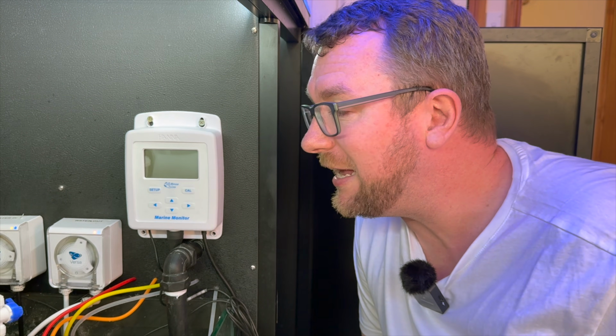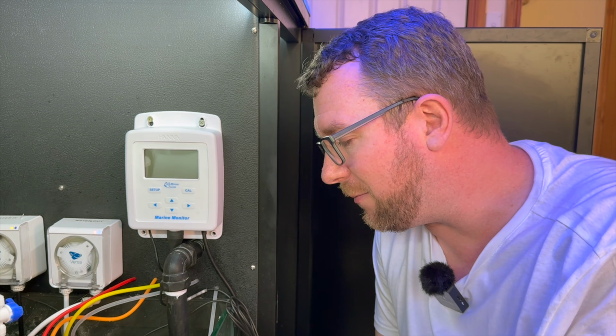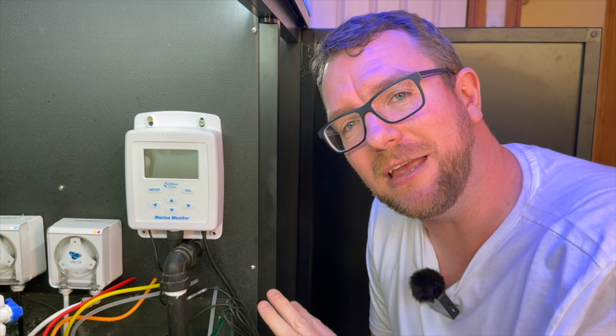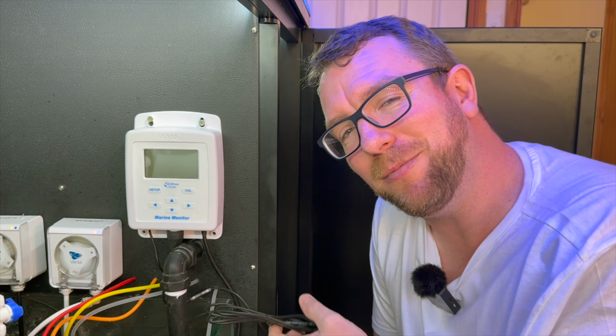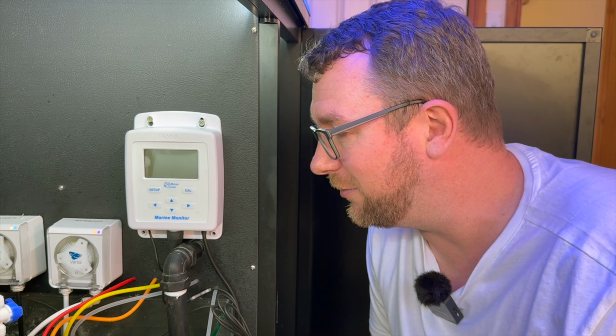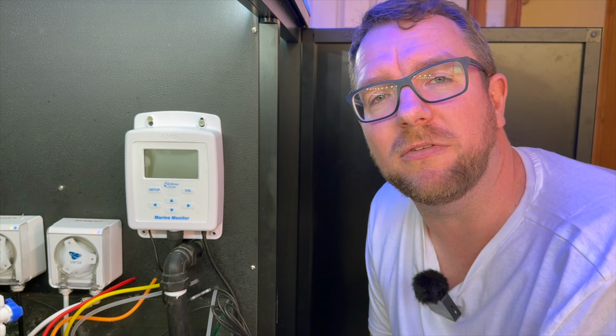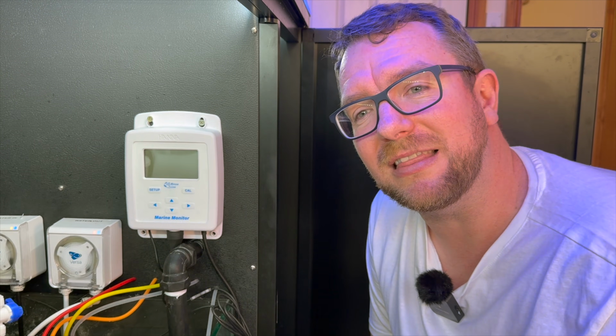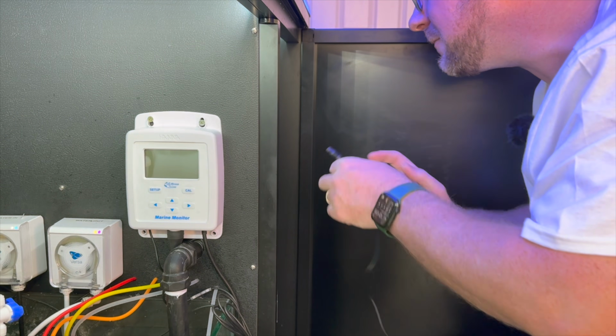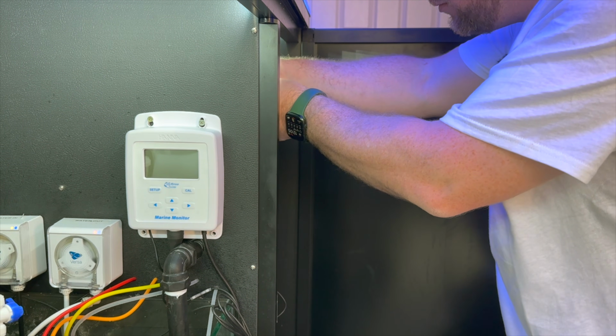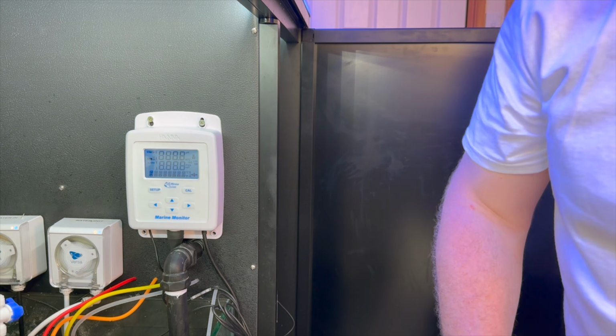Alright, so I've got the Marine Monitor all mounted up here on the inside wall of my Cade frag tank cabinet, and I've got my conductivity and pH probes in place, albeit fairly temporarily with the cables out here, but it is going to be more than adequate for the use case. Now, the instructions do tell me that the next step is to power it on and then go through the menu and set the bounds for the low limits and high limits of each of the parameters. Doesn't actually say anything about calibration at this stage, but rest assured we'll go through the calibration process just so you know what is involved. But all I really need to do now is grab this power cable here and plug him in. And see what this unit does.